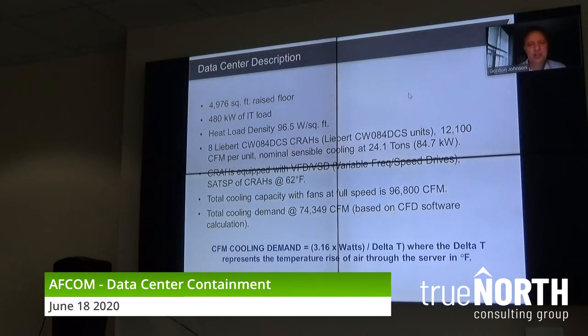In the past, and even if you Google this after this meeting, if you ask how much CFM do I need to remove 1 kW of heat, unfortunately the answer you're going to keep coming up with is 158 CFM. So a 5 kW rack in your data center would be 5 times 158, whatever, 750 or somewhere around that. That was true 10 years ago. That's true in your telecom days. That's not true today. Now, if you're in an older data center and all the server racks are 2 to 3 kW, that's probably a fair number to go with.